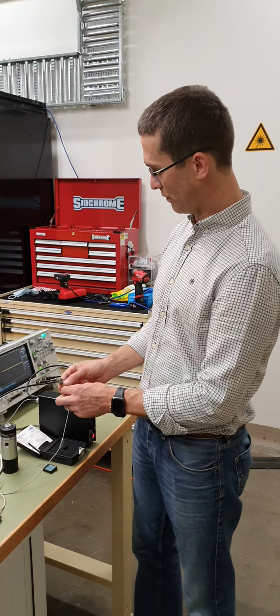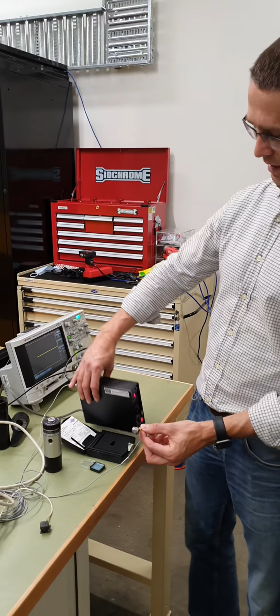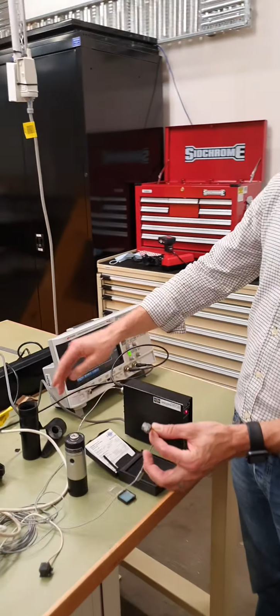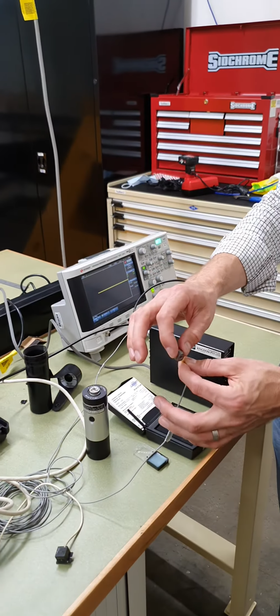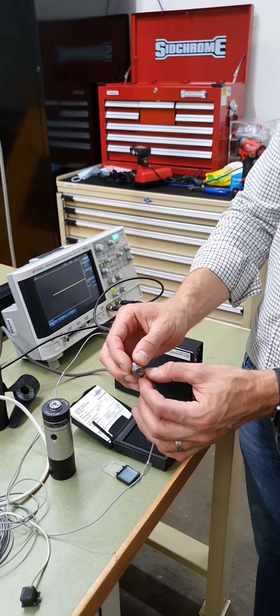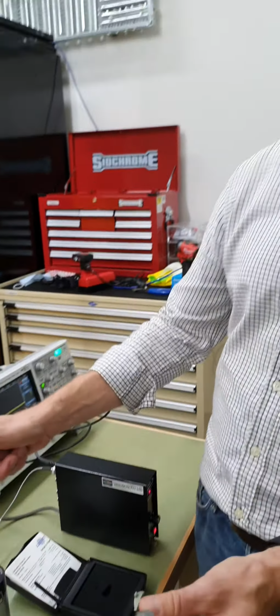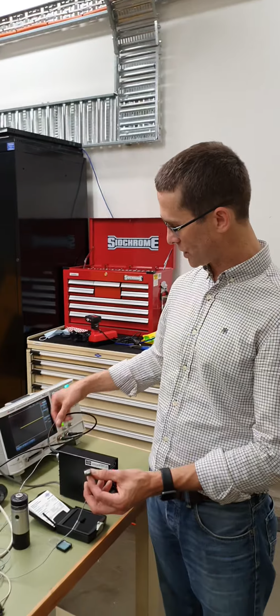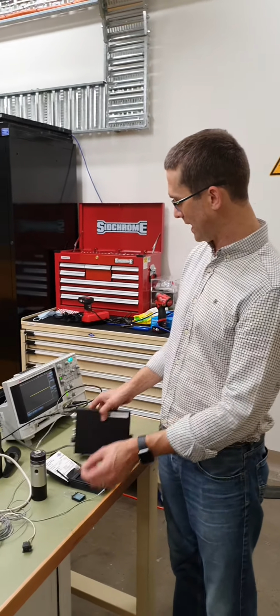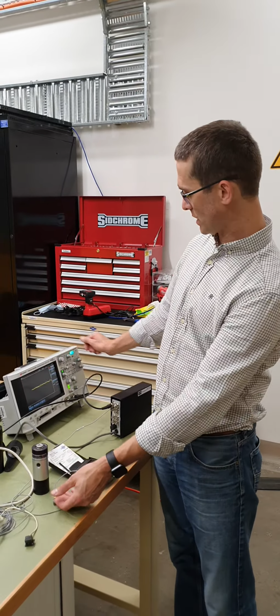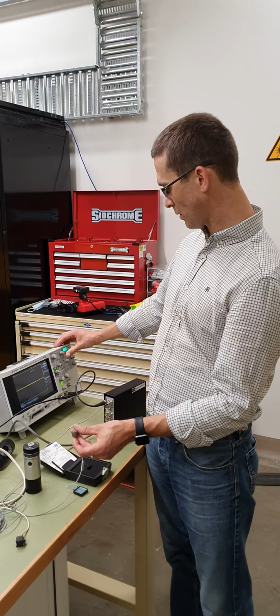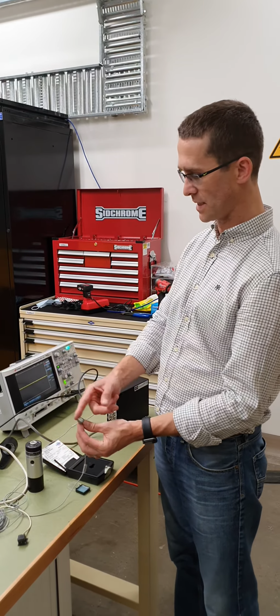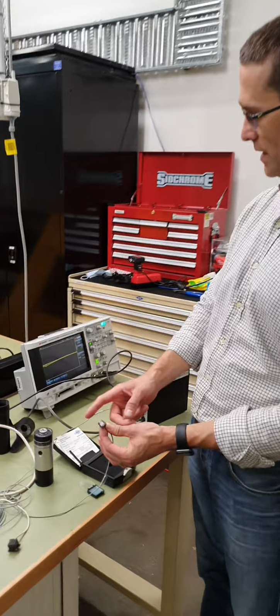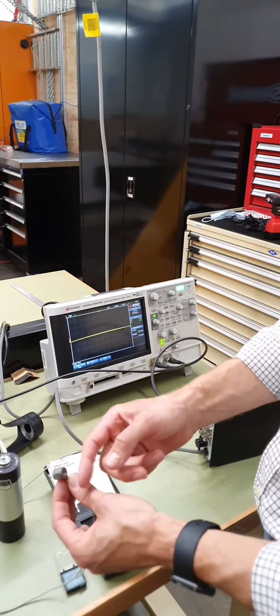A voltage is provided via an IEPE power supply over the cable, and the electronics amplify the measurement and modulate that voltage such that the voltage can be measured back in the system that we're using, the acquisition system that we're making the measurement in. So as I tap the transducer, you can clearly see it's making a measurement of the vibration.